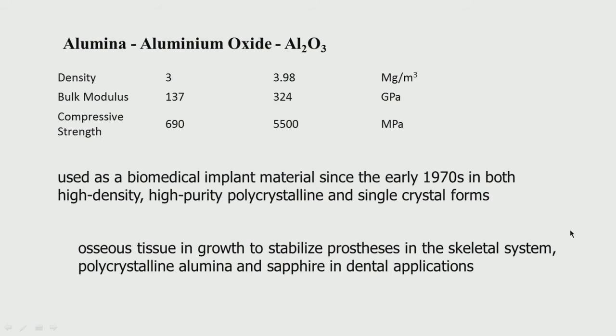Let us look a little bit at each one of these biomaterials. The oxides — alumina (aluminium oxide, Al2O3) — has a certain density, bulk modulus, and compressive strength. It has been used as a biomedical material since the early 1970s in both high density, high purity, polycrystalline and single crystal forms. It is used in osseous tissue ingrowth to stabilize prosthesis in the skeletal system, polycrystalline alumina and sapphire in dental applications. It is found mostly in fillers, bone replacement, and coatings in orthopedic and dental filling.